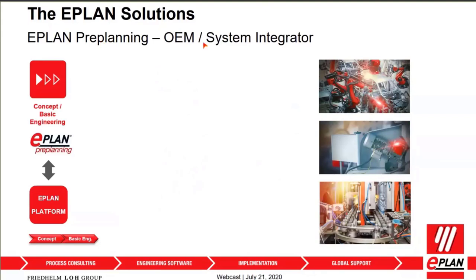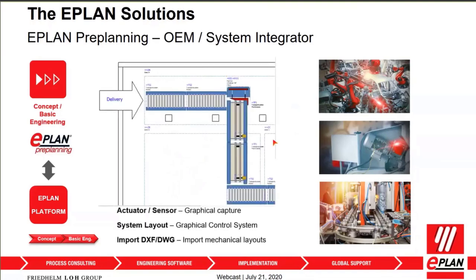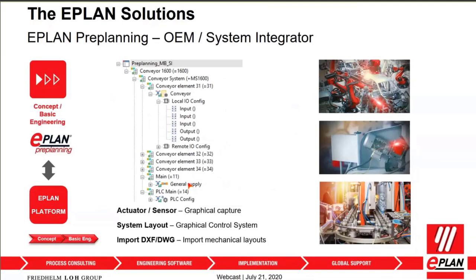ePlan preplanning can also be used for OEM and system integrators. Using a blank canvas, you can graphically lay out your mechanical system — for example, a conveyor system with different segments. As you lay out your system graphically, you capture both a location structure and identify all actuators and sensors. Right upfront in the planning phase, you can understand how many motors, IOs, and signals you will need, and use it for quoting. You can import DXF or DWG drawings from AutoCAD as a graphical background and capture your control system on top.